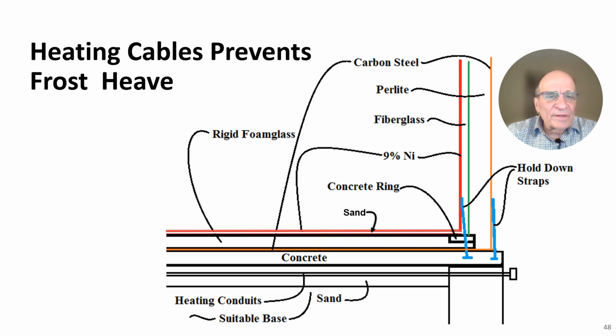This is nothing more than a closer picture of the configuration of how you'd have your heating system provided for a tank. Now, this is for tanks that are on the ground. There are some tanks that have a space between the bottom of the tank and the ground, and those tanks are set on piles and pile caps. So you have a bunch of piles in the ground, and then you have the tank sitting on top of that with maybe a 2-foot air gap between the ground and the bottom of the tank.